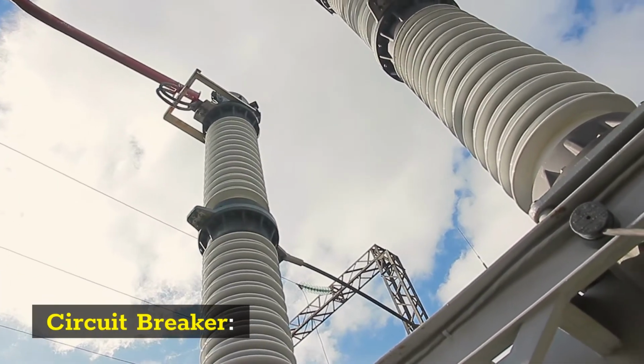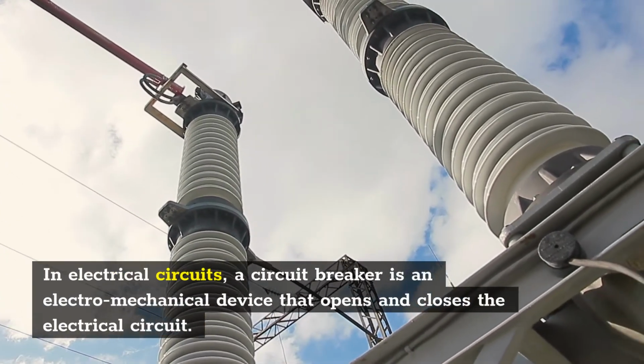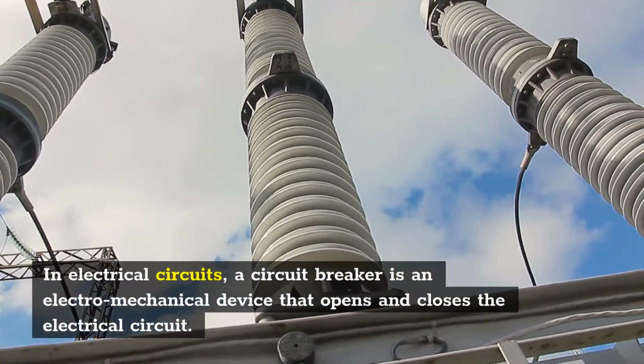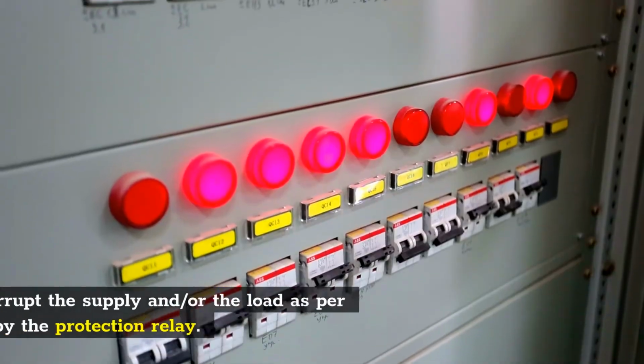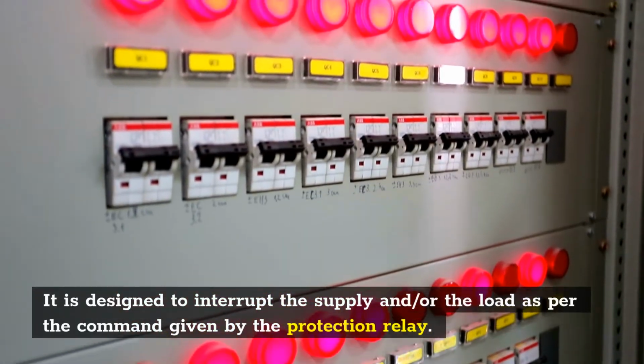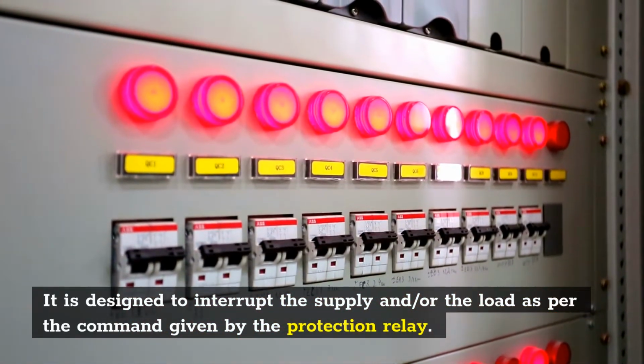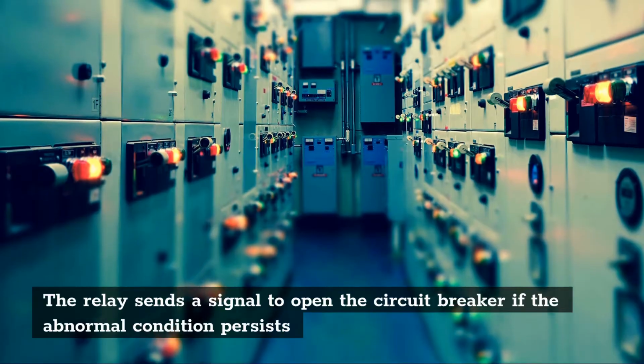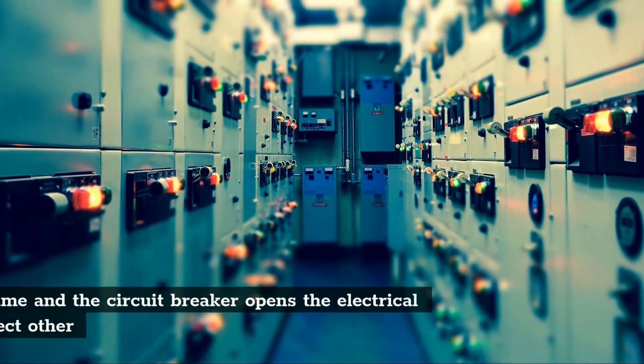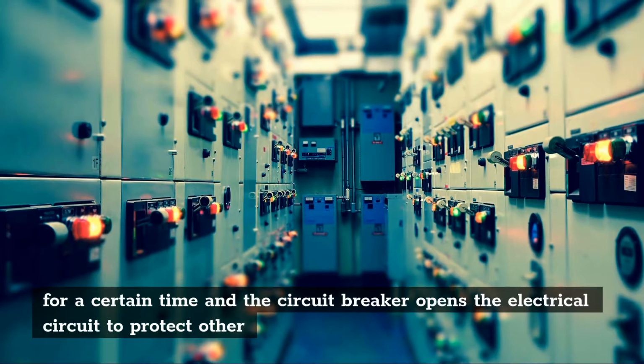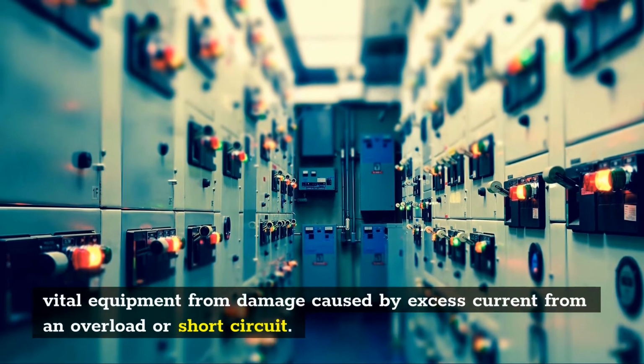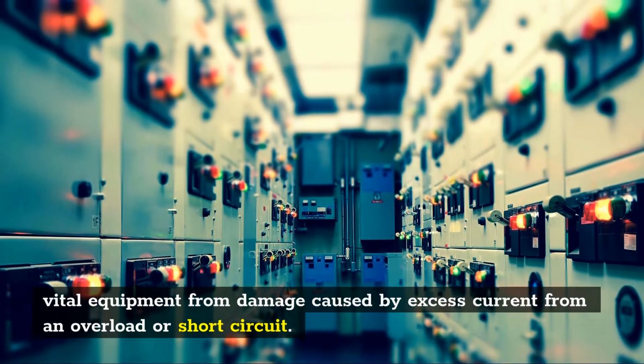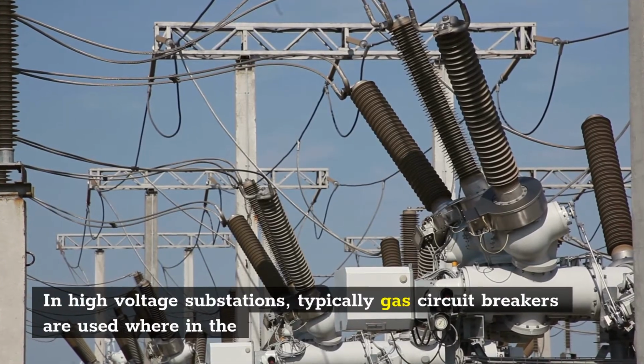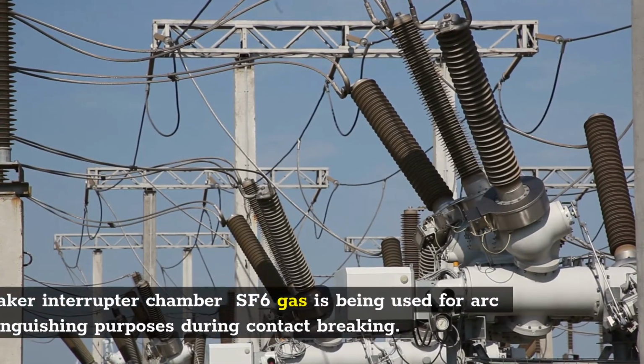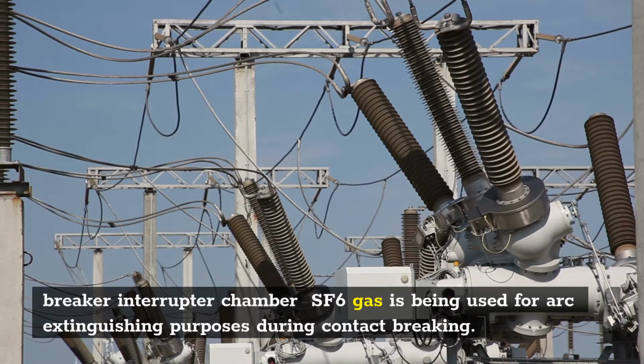Circuit breaker. In electrical circuits, a circuit breaker is an electromechanical device that opens and closes the electrical circuit. It is designed to interrupt the supply and/or the load as per the command given by the protection relay. The relay sends a signal to open the circuit breaker if the abnormal condition persists for a certain time, and the circuit breaker opens the electrical circuit to protect other vital equipment from damage caused by excess current from an overload or short circuit. In high-voltage substations, typically gas circuit breakers are used, where in the breaker interrupter chamber SF6 gas is used for arc extinguishing purposes during contact breaking.